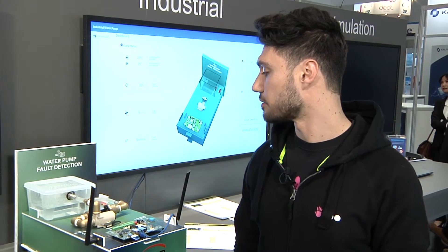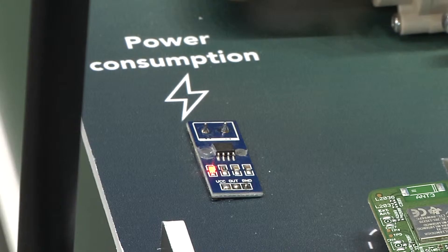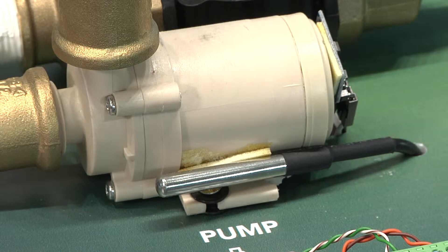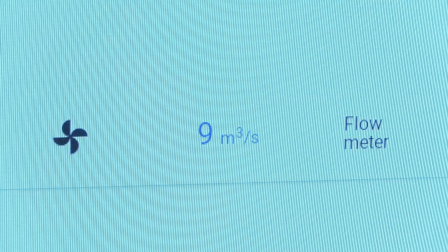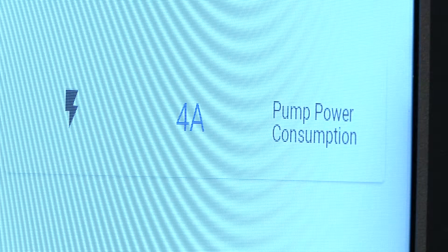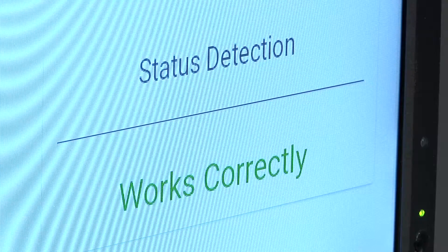We are collecting data from different sensors: power consumption of the pump, the temperature of the pump, the humidity and temperature of the environment, the flow meter, and the fluid sensor. With these different sensors combined in a machine learning algorithm, we can detect the chance of a fault on the system.